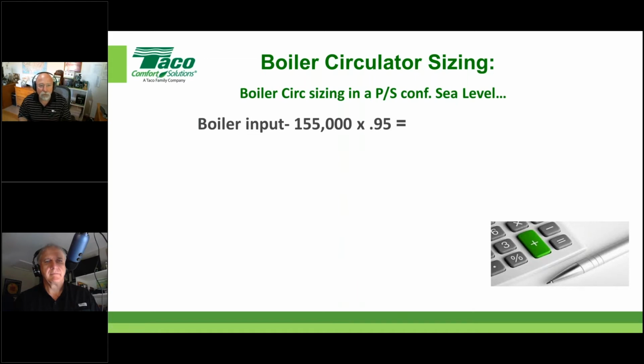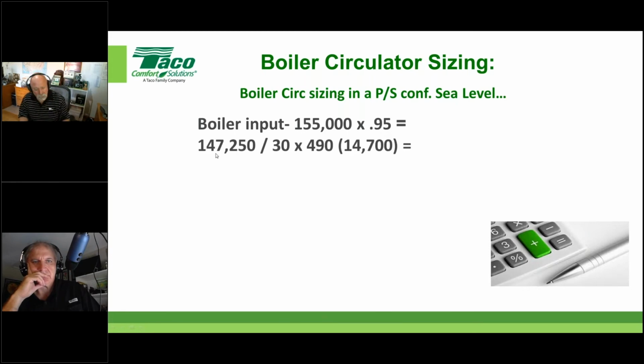If we had that boiler input of 155 at sea level, I'm showing you a couple of examples here. 0.95, right? 0.95 means you're going to say this boiler is operating at its highest efficiency. That would be your AFUE of 95. So that gives us 147,250. That's just taking 5% off, right?